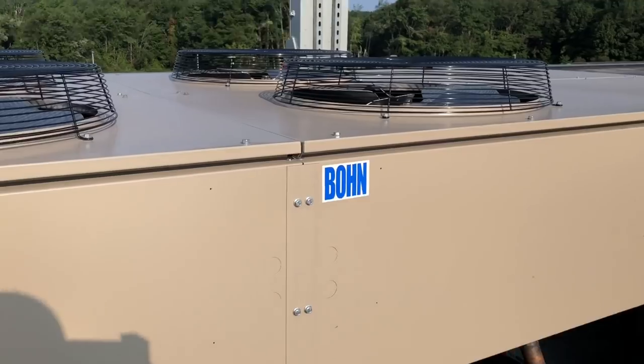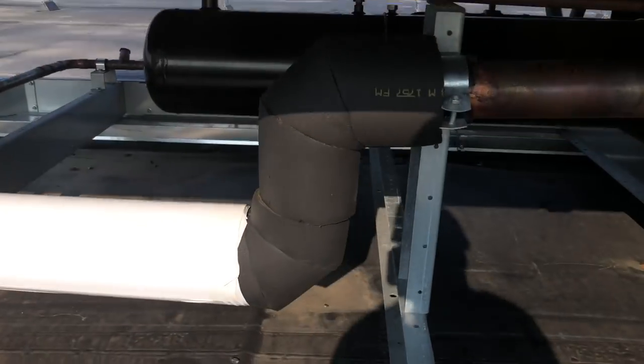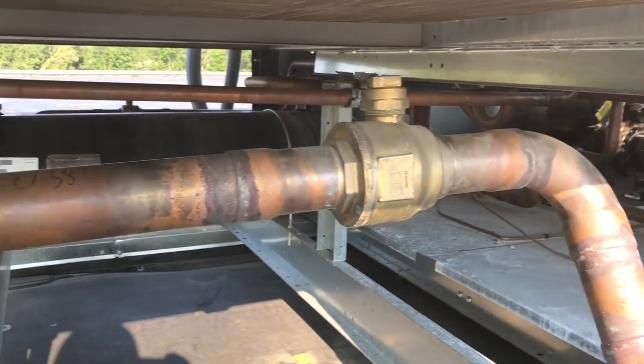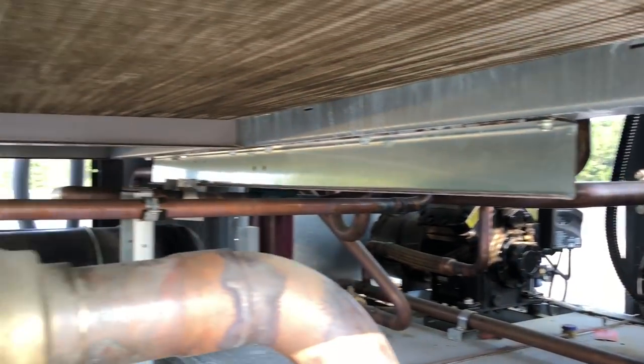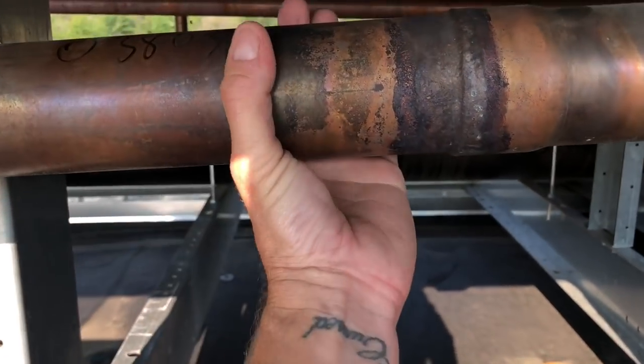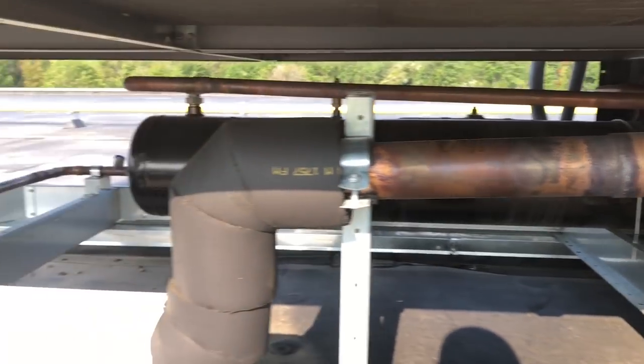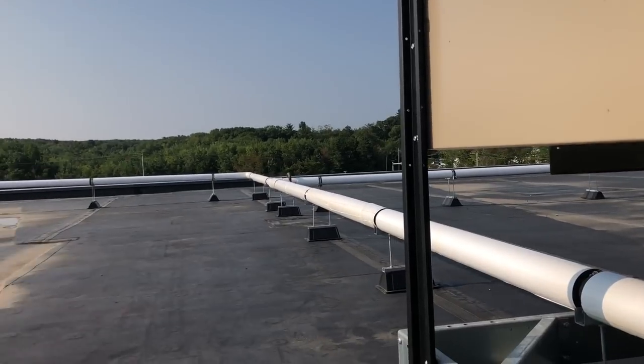Back again, going to show you a bit of these 60 horse units here. He's got Armaflex on it, but look at the suction lines on these things. You can see with the sun in here — my hand right there, I can't even go around it. That's a two and five-eighths suction line that goes down, then gets reduced down to two and one-eighth going into the evaporators.